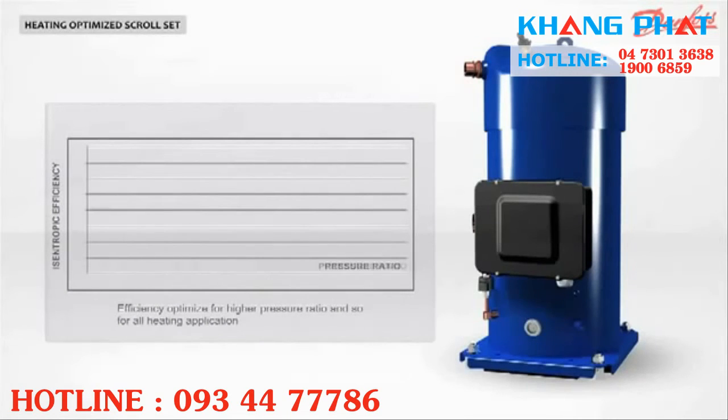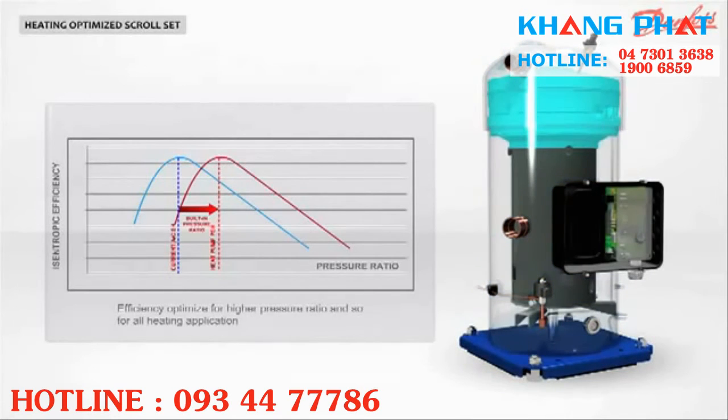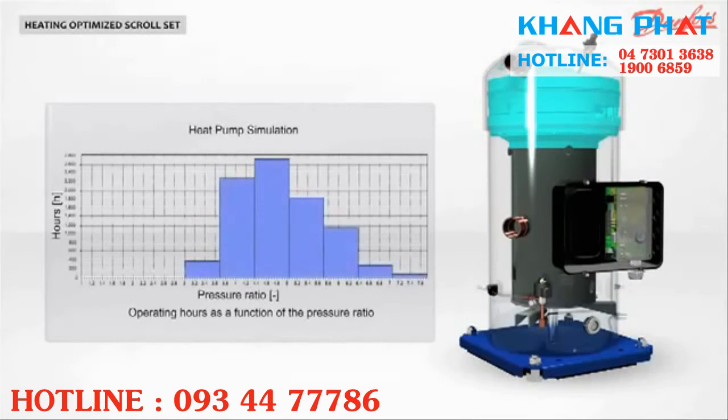The peak isentropic efficiency of a scroll compressor is determined by the design of the scroll set. The Performer PSH has a scroll set optimized for high pressure ratio. A heat pump will operate with a high pressure ratio most of the time. As a result, the PSH seasonal efficiency is higher than that of a standard compressor.